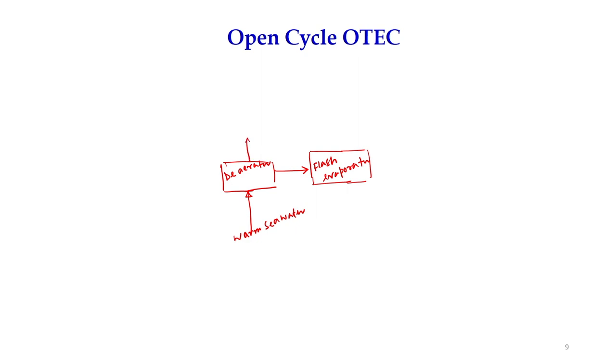So these gases have to go out, and here we can have a vacuum pump, and it will release the non-condensable gases. And then once we have the flash evaporator, when this seawater enters here, it is maintained in such a way that pressure will drop. Once pressure drops, sudden vaporization will start. So when you reduce the pressure below the saturation point corresponding to that temperature, it will evaporate, right?